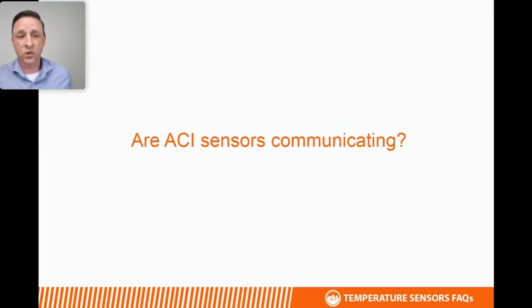Are ACI sensors communicating? Some are. We do offer a full line of BACnet, MSTP, and Modbus communicating devices. But our standard thermistors and RTDs and transmitters are not communicating in the way that a BACnet or Modbus protocol is. Standard thermistors just output a signal. They're not designed or able to do two-way communication or be daisy chained together to allow for multiple sensors off of one power supply.